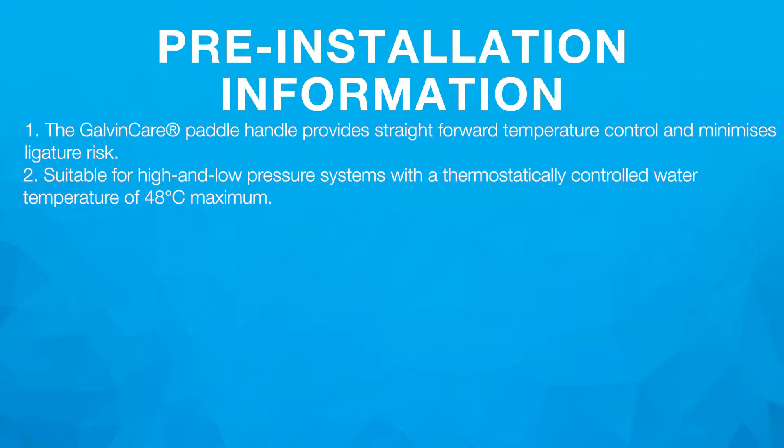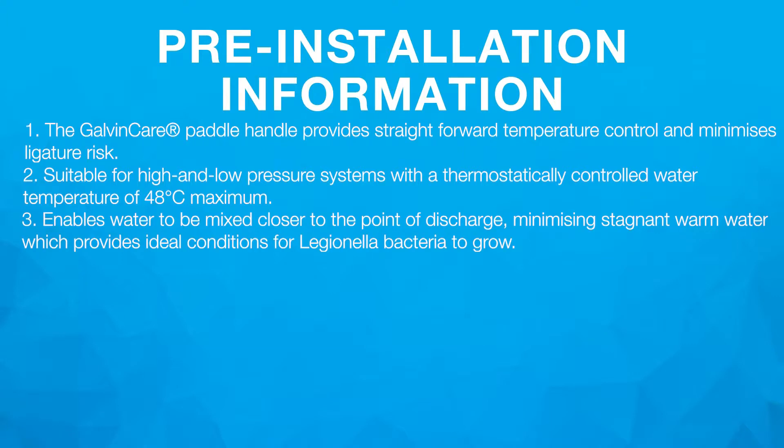2. Suitable for high and low pressure systems with a thermostatically controlled water temperature of 48 degrees Celsius maximum. 3. Enables water to be mixed closer to the point of discharge, minimising stagnant warm water which provides ideal conditions for Legionella bacteria to grow.